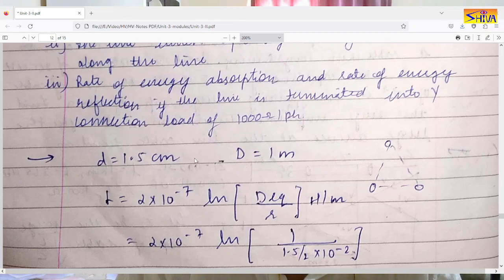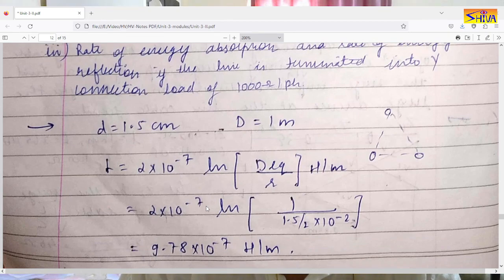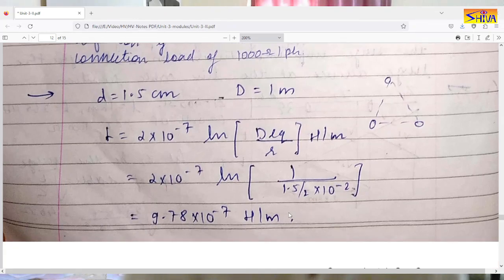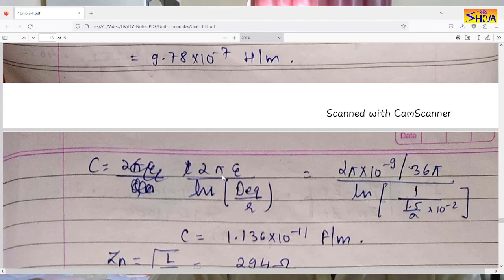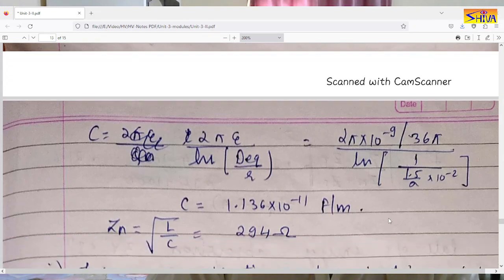For no reflection, the terminating impedance must equal the surge impedance. The surge impedance is √(L/C). Inductance: L = 2×10⁻⁷ × ln(D_eq / r) H/m. With D_eq = 1 m and r = 0.75×10⁻² m, L = 9.78×10⁻⁷ H/m. Capacitance: C = 2πε / ln(D_eq / r) = 10⁻⁹/(36π) / ln(1 / 0.75×10⁻²) F/m, giving C = 1.136×10⁻¹¹ F/m.